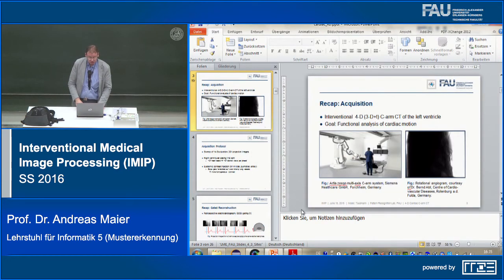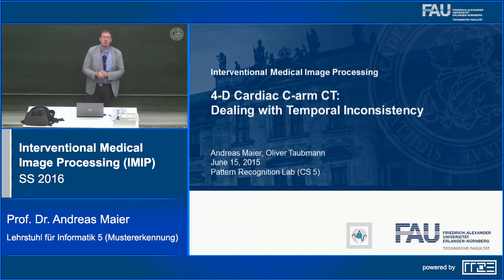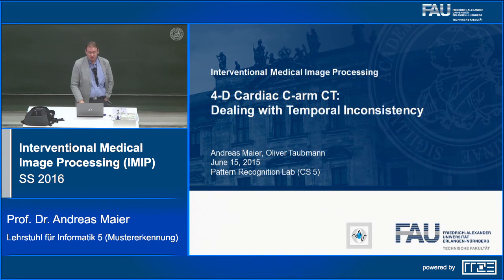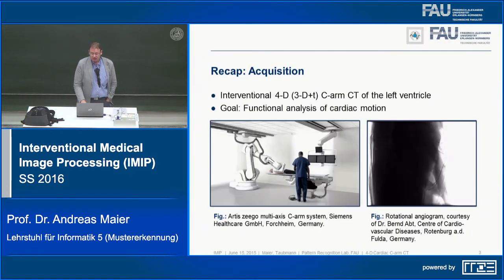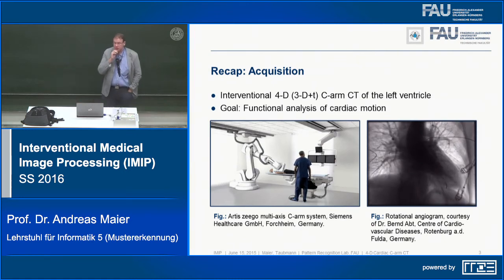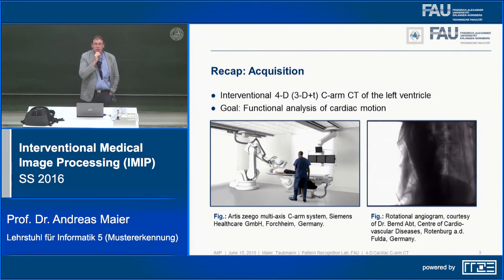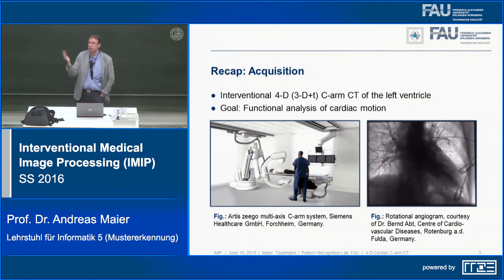Now extending these ideas further: we want to reconstruct the entire volumetric images, not just coronary arteries — including soft tissue slice images of the heart. A recent method published last year deals with temporal inconsistency. Rather than back-and-forth multi-sweep protocols, we now use only a single sweep of 14.5 seconds duration acquiring almost 400 projection images, omitting the back-and-forth sweeping procedure.